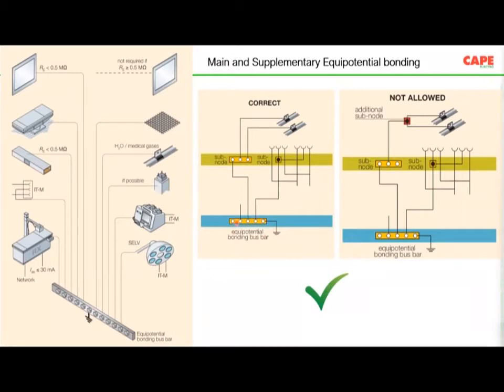at the mains incoming panel, we are supposed to make an earth bus bar, and the exposed and extraneous conductive parts must be connected to this particular bar. Then at the sub node, let us say, for example, the operation theater, you are supposed to have supplementary equipotential bonding. On the left side, you can see how the supplementary equipotential bonding is made. You have to have a bus bar large enough to accommodate each and every connection separately. So individual earthing means each and every medical item must be connected to this bus bar separately. This means you are not supposed to make a loop.